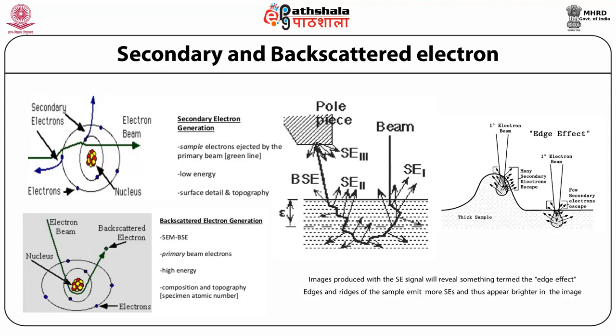Secondary electrons are generated by three different mechanisms: SE1, SE2, and SE3. SE1 secondary electrons are produced by interaction of electrons from the incident beam with specimen atoms, generated in close proximity to the incident beam and thus representing a high lateral resolution signal. SE2 are produced by interaction of high-energy backscattered electrons with specimen atoms, carrying both lateral and depth distribution characteristics of the backscattered electrons. SE3 are produced by high-energy backscattered electrons that strike the pole pieces and other solid objects within the specimen chamber.